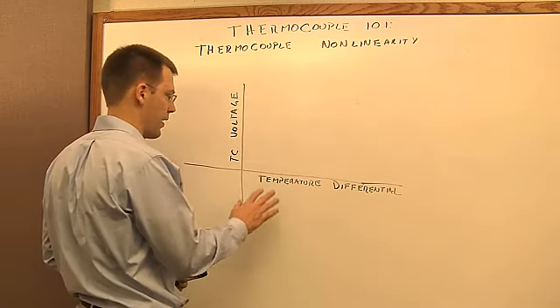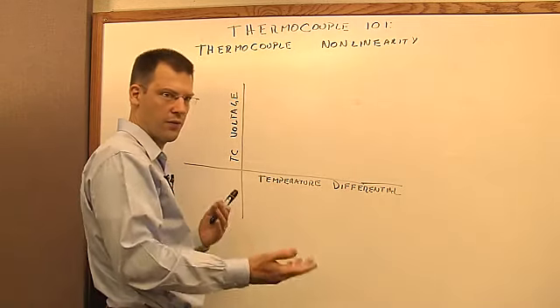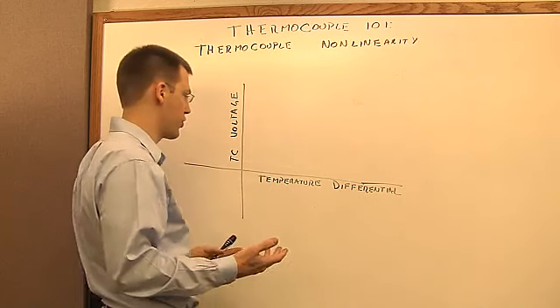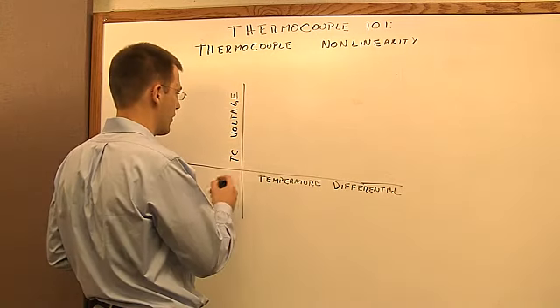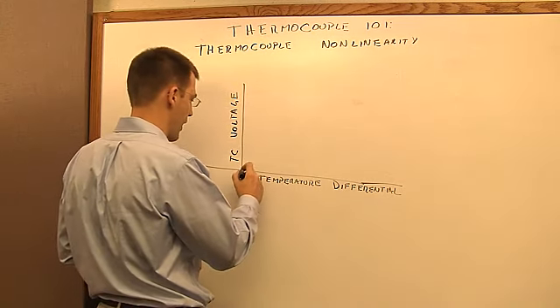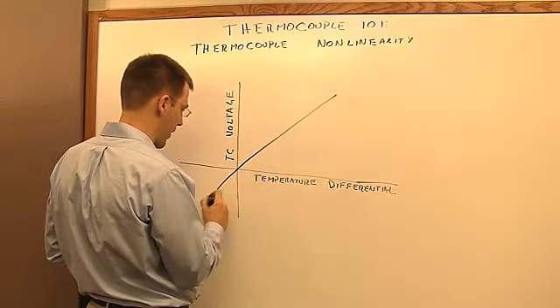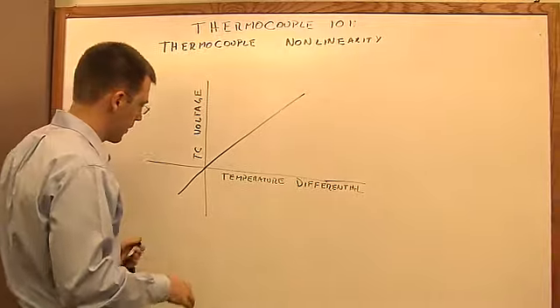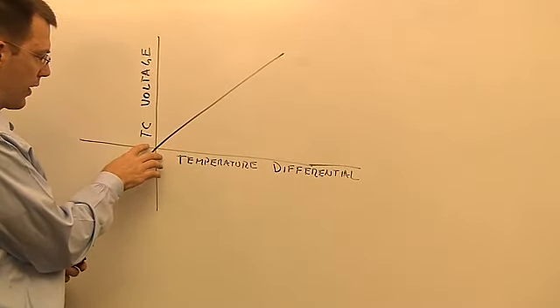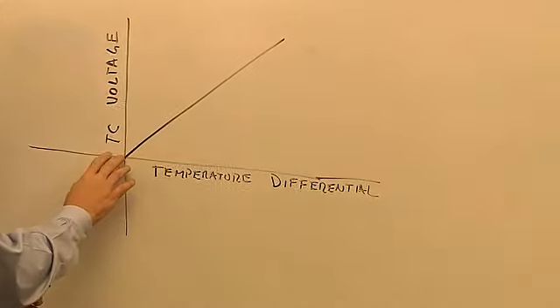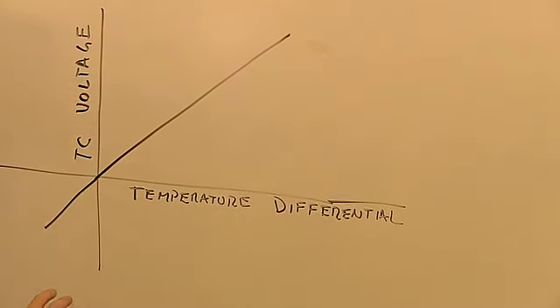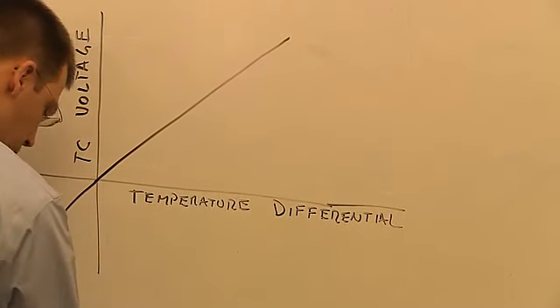If you were to plot the temperature differential, so the difference between the measurement junction and the reference junction, versus the thermocouple voltage that you get out of the thermocouple, you'd get something that looks pretty straight. Notice that the line goes through when there's no temperature differential, you're not going to get any voltage out, and you get something that to the naked eye looks pretty straight.